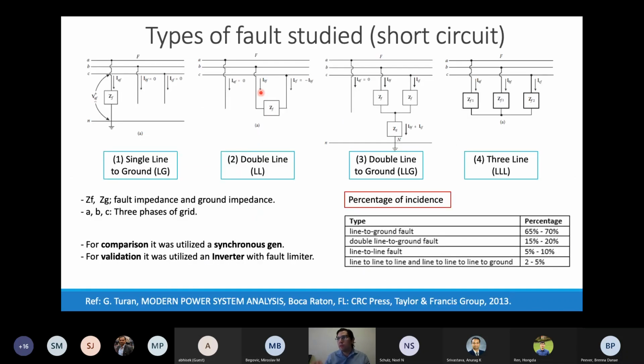So these are the most common short types of faults that exist: the single line to ground fault, the double line to ground, and the triple line. We know that the incidence of these faults is about 70% for the single line to ground fault, which is the most common one, followed by the double line to ground fault, which is 20%. We have a line-to-line fault, which is 10%, and we have the triple line fault, which is 5%, which is the least common but the most critical. But all of them are critical in our study, to be clear. We utilize a synchronous generator for comparison, and we use the inverter to validate the response of them, in current research and experimentation.